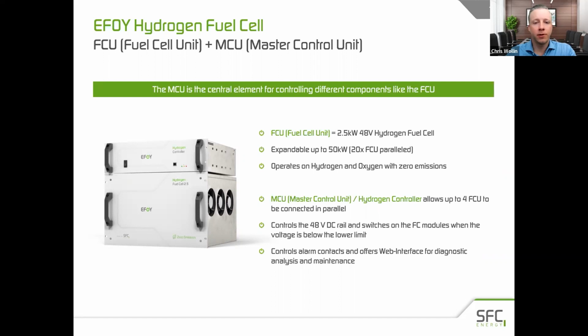The hydrogen controller itself is the central control device for the various components of the system. It controls the parallel operation of up to 4 fuel cell units together, in addition to controlling the 48 volt output and the switching on and off of the fuel cell as required when the voltage thresholds are reached.